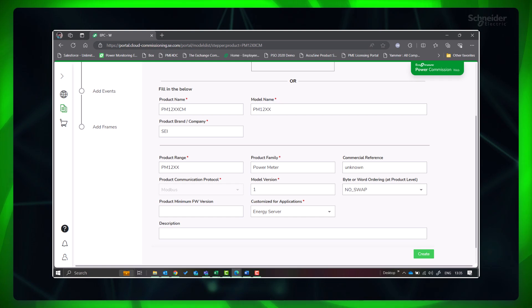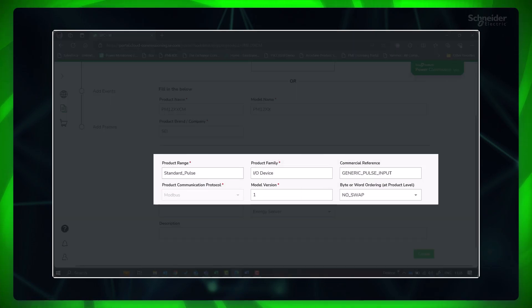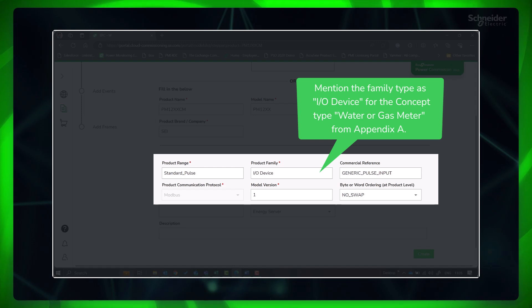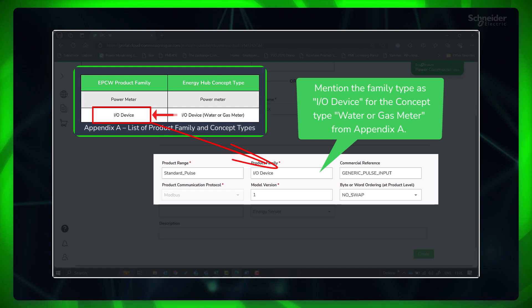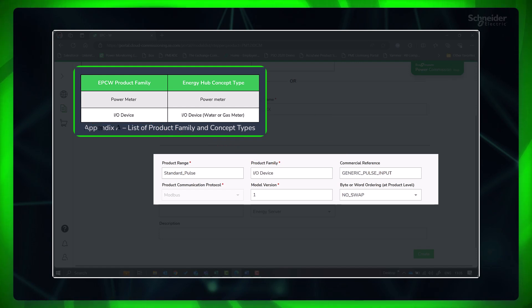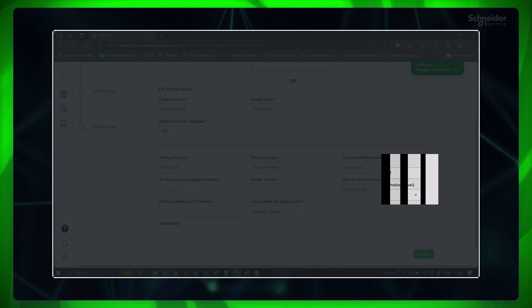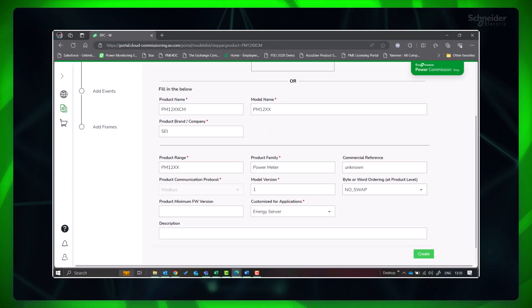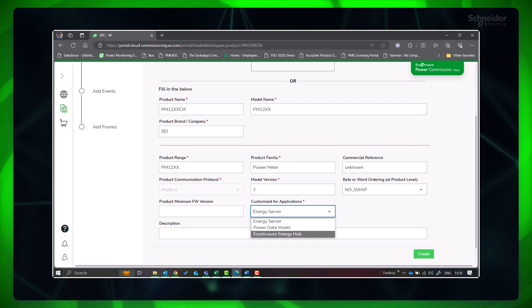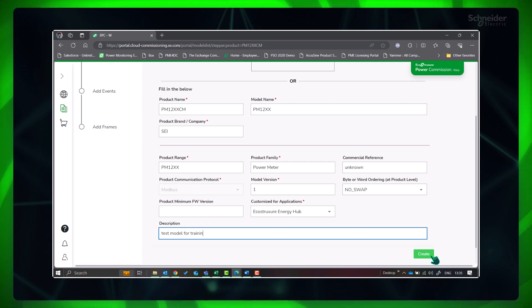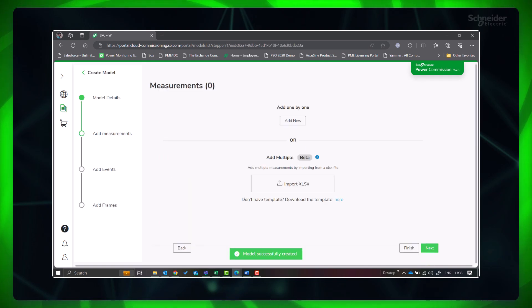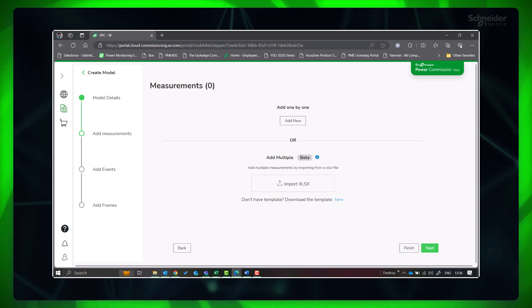While providing the product family, please make sure it matches with an Energy Hub concept type. For a Modbus power metering device, 'Power Meter' will be the concept type. Commercial reference should be left blank. For water or gas meters, 'IO Device' will be the concept type, and the same is to be filled for product family. For product range, 'standard_pulse' should be given, and in place of commercial reference, 'generic_pulse_input' should be mentioned. For 'Customized for Applications,' select EcoStructure Energy Hub from the dropdown. If byte swapping is enabled at product level, select the same; otherwise keep the default 'No Swap.' Provide a description if needed and click Create.